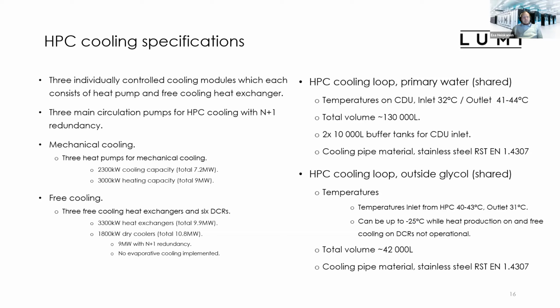In addition to that, we have free cooling with the free cooling heat exchangers and the 6 dry coolers. Each one of these consists of 3.3 megawatt heat exchangers, and we have a total of a little bit over 10 megawatt of dry coolers installed on our roof. Even with the N+1 redundancy, we still have 9 megawatts of free cooling capacity installed. And as we are operating so high in the north, we haven't needed to implement any evaporative cooling method for the dry coolers, so we are able to operate around the year with the free cooling. I will get more detail on this later.